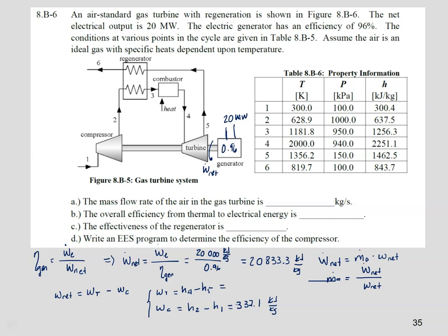The turbine work is h4, which is 2251.1, minus h5, which is 1462.5 — giving 788.6 kilojoules per kilogram. Doing the subtraction, the net work is 788.6 minus 337.1, which equals 451.5 kilojoules per kilogram.